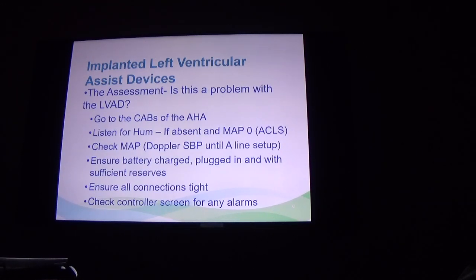If you hear a hum, that means the motor's working. That means the pump's working. If it's absent and you have no MAP, MAP is 0, you're going to have to start compressions. I know people say, oh, don't start compressions on LVADs. Well, if their MAP is 0 and there's no hum, it means the device is not functioning. There's only one thing you can do, and that's compressions.